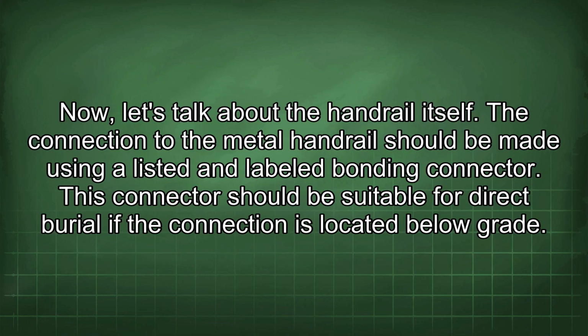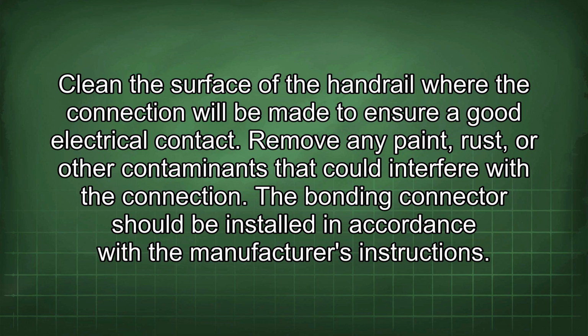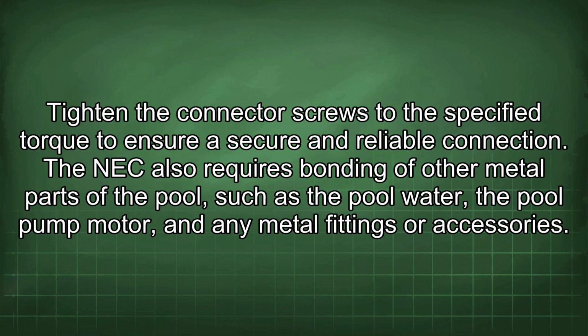Now let's talk about the handrail itself. The connection to the metal handrail should be made using a listed and labeled bonding connector. This connector should be suitable for direct burial if the connection is located below grade. Clean the surface of the handrail where the connection will be made to ensure a good electrical contact. Remove any paint, rust, or other contaminants that could interfere with the connection. The bonding connector should be installed in accordance with the manufacturer's instructions. Tighten the connector screws to the specified torque to ensure a secure and reliable connection.